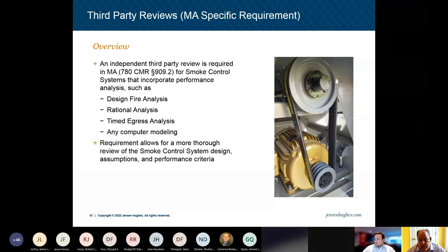All right. So as you can kind of see, the picture on the right is actually a stair press fan in there, similar to a fire alarm system having redundant reliability with Class A or Class X circuits. Smoke control systems also have redundancy in things that need to be built into them. This example is of a mechanical system that has a 3-belt pulley system. So there's actually 3 belts in there. And the code requirement is to have a 50% redundancy of the belts. So this belt, for example, this system, 2 belts is what the normal load would be. They have to add a 3rd belt just in case one of those belts breaks. So there's a lot of nuances and pieces and parts of the overall smoke control system. Like Carson had mentioned, it's a kind of an integration of all kinds of different systems.